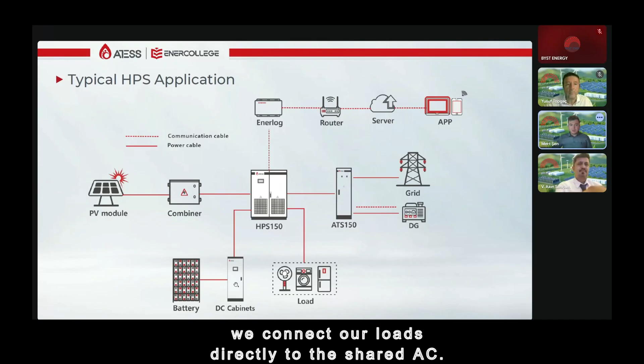The main difference between these and battery inverters is that loads are connected directly to the shared AC. With our HPS hybrid models, we pass the clean energy through the inverter, ensuring a clean energy supply. This hybrid inverter allows us to adapt the existing system on the customer's roof or next to their factory. Instead of using the bypass capability, we install a distributor and collector cabinet at the output of the hybrid inverter, called the MDB combiner unit.